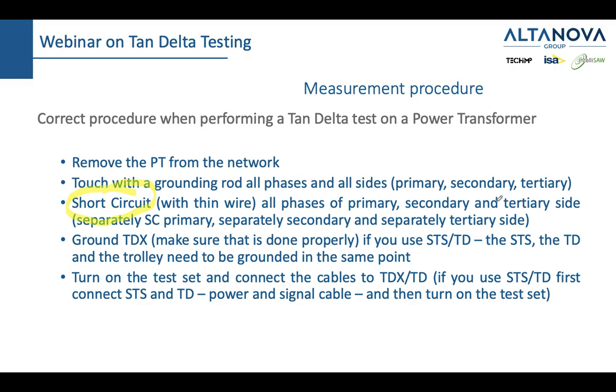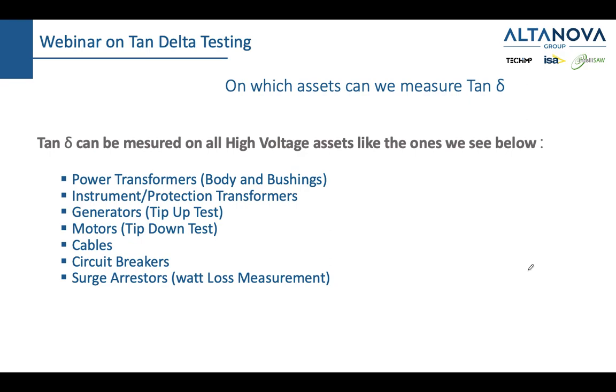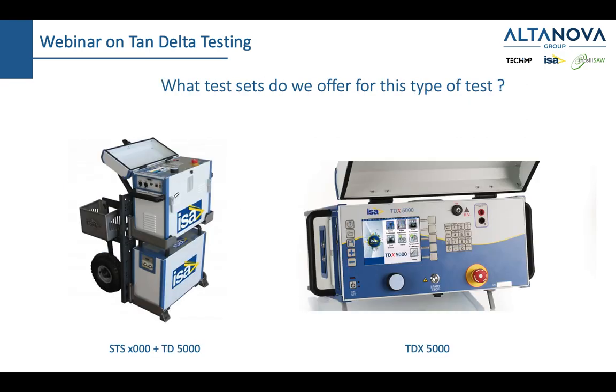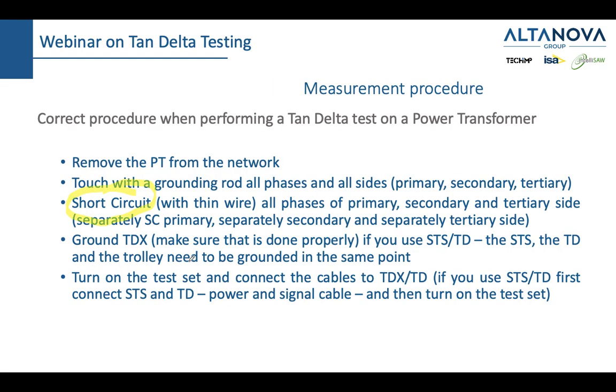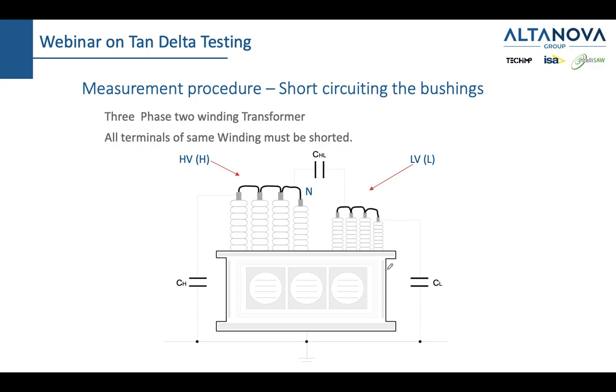If you are now testing, the next step would be, if you have STS and TD, before you turn them on, you would connect these two boxes, and then you would turn them on. Don't connect them while they are on. And if you have a TDX, since it's a one-box solution, you don't have to do any connections. So this is showing you how the short circuit is done on the primary side, and how the short circuit is done on the secondary side.